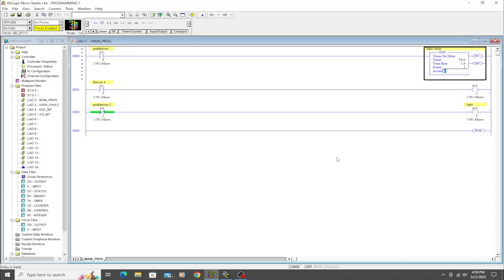This is asking the time base, so whether it be like one second or milliseconds or whatever you want to use. We're just going to use full seconds here. And then right now it's asking us the preset, so this is the preset amount of time that you want it to take for this timer to complete. We're just going to do five, meaning five seconds.